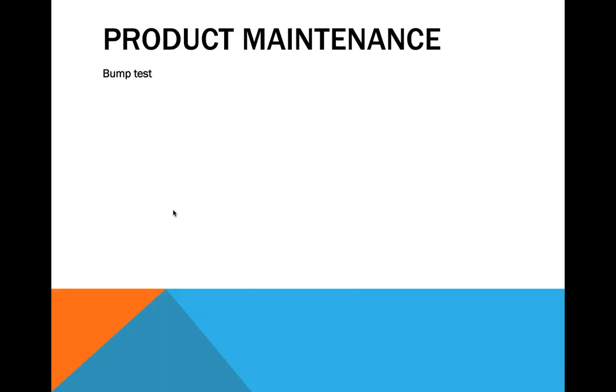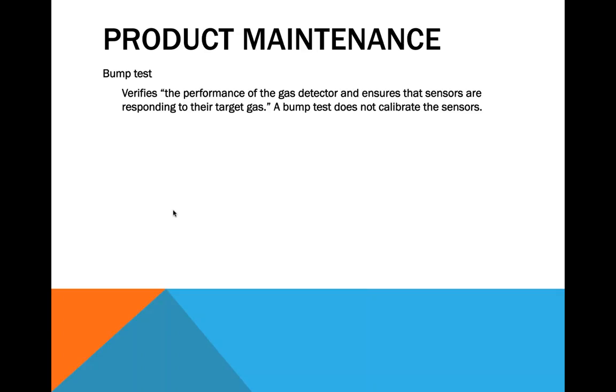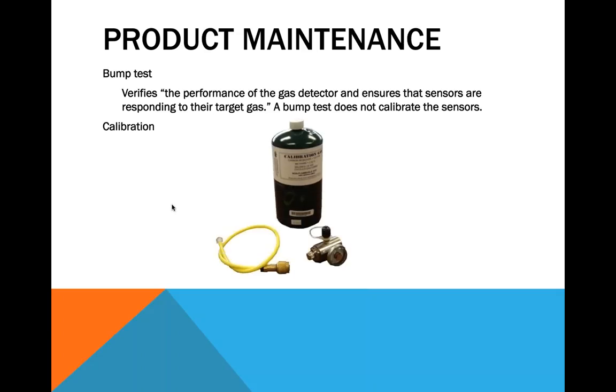Now jumping over to product maintenance, there's something called the bump test, which verifies the performance of a gas detector and makes sure the sensors are responding to the target gas. It's sort of like giving an elbow to your buddy sitting next to you to make sure he doesn't doze off during a company meeting. You want to make sure he's awake. You didn't actually take his pulse or his heart rate or his temperature by the bump. You just bump him and make sure some basic performance is going on. So it does not calibrate the sensors, but it verifies the detection of the gas.